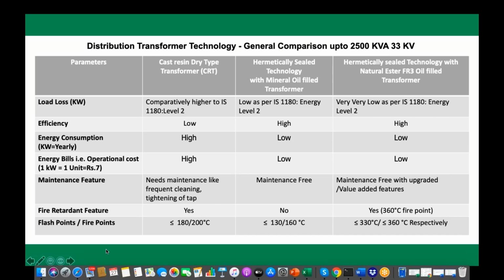The maintenance practices, a lot of people may say, I mean, I used to say dry type are maintenance free, and yes, they are maintenance free. They don't need a maintenance which associates with liquid, if any leakage or something, but they need a significant maintenance to clean them weekly, unless you have a sealed transformer like in East India, CSC uses sealed transformer, but except them, all other places are ventilated dry type transformer.